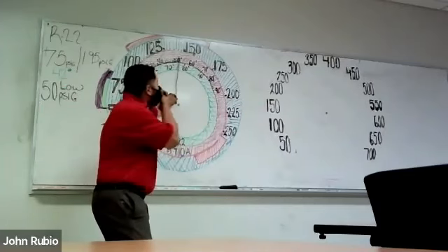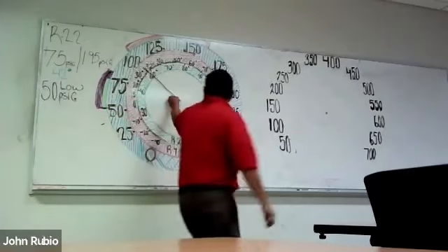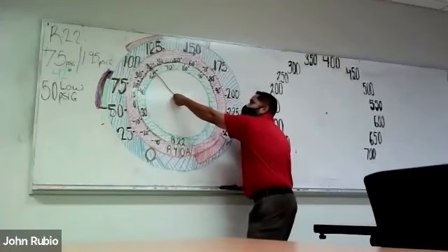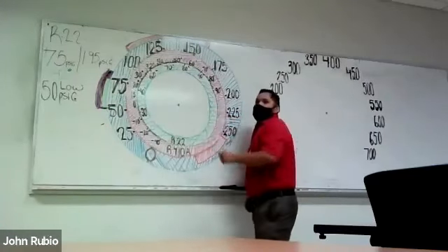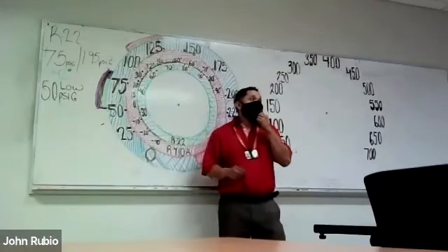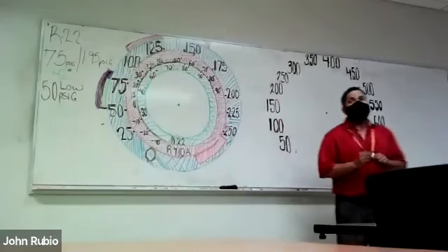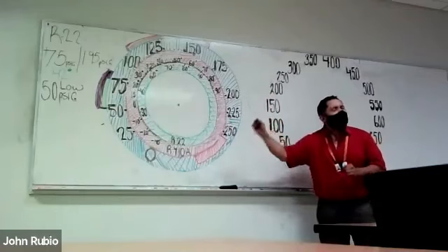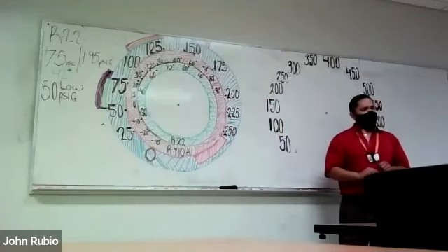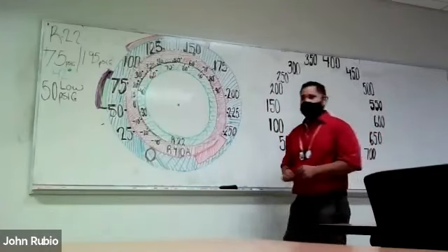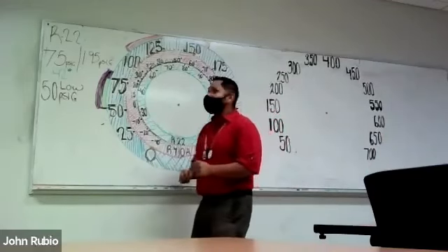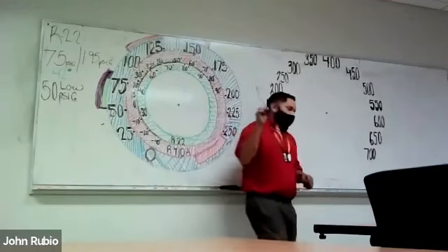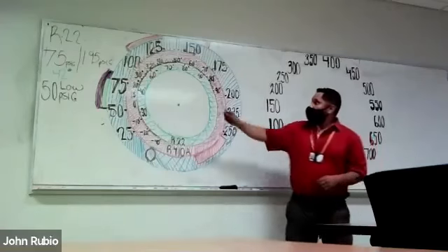Meaning, when you get to a job and your refrigerant pressure is in the bottom range, now you can say, when I add, I will increase performance. And when we get to superheat, you'll see how we use our temperature probe to monitor in real time the performance increase. We can take a digital picture of the performance increase when we find a superheat.